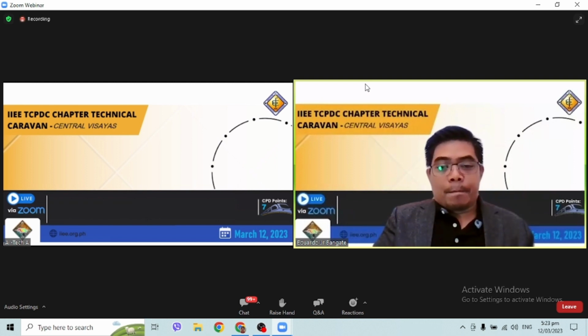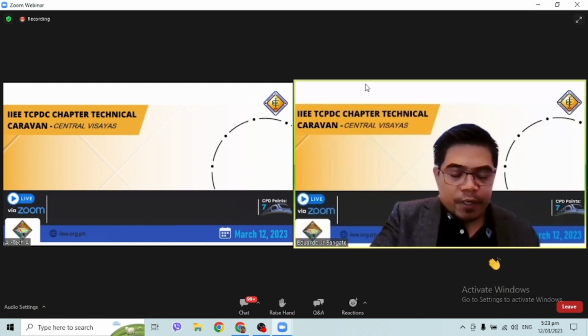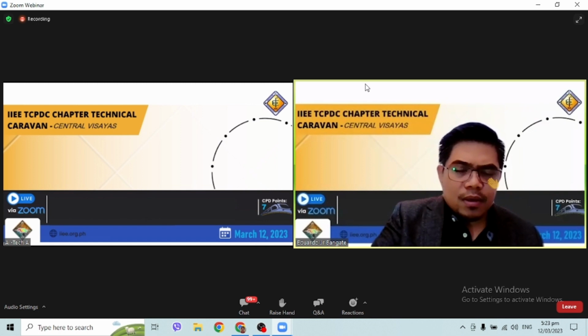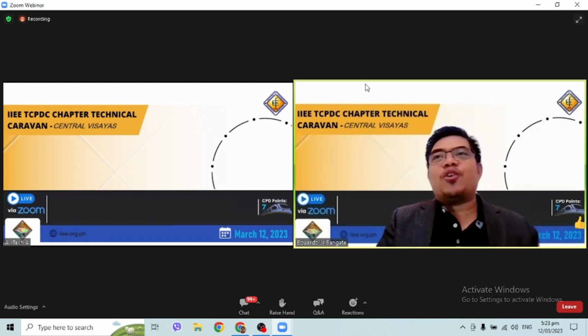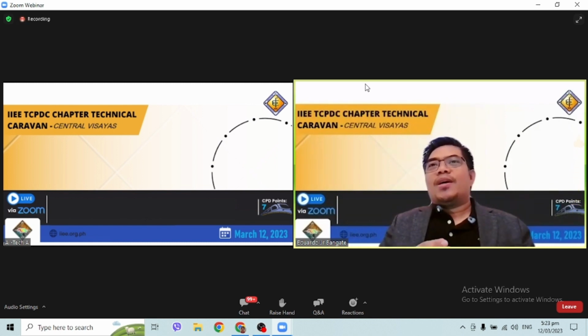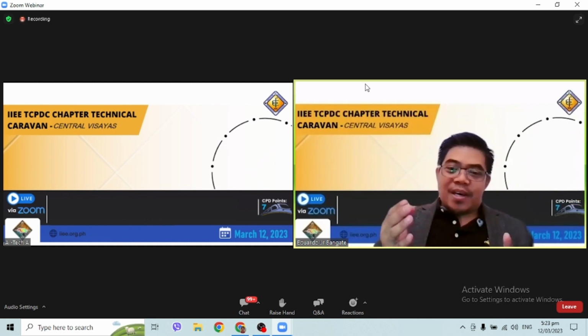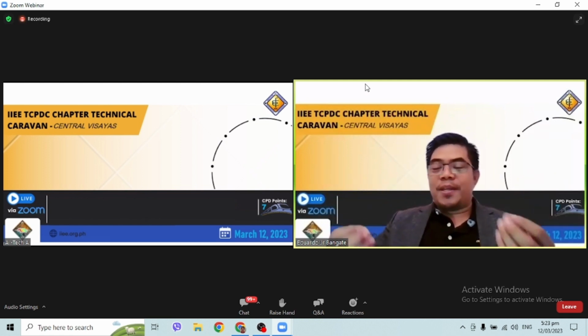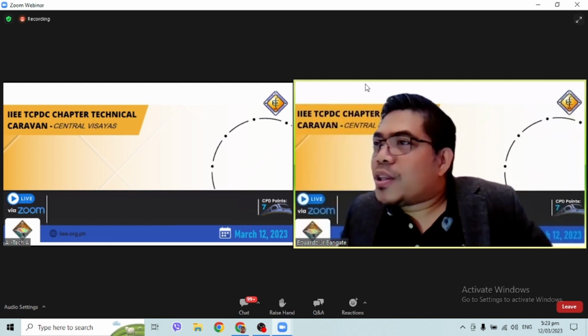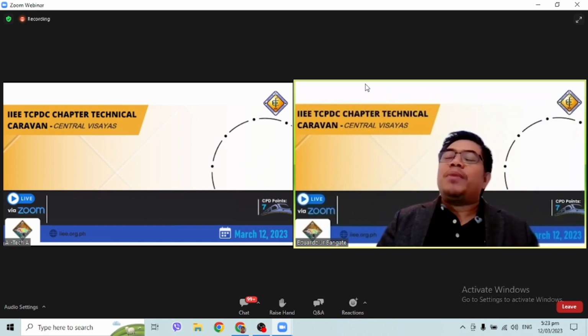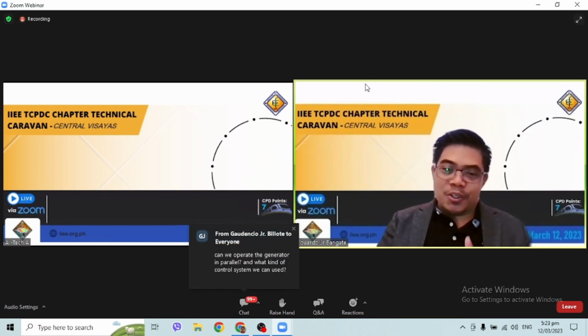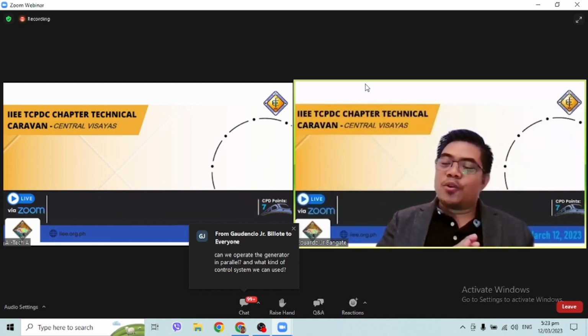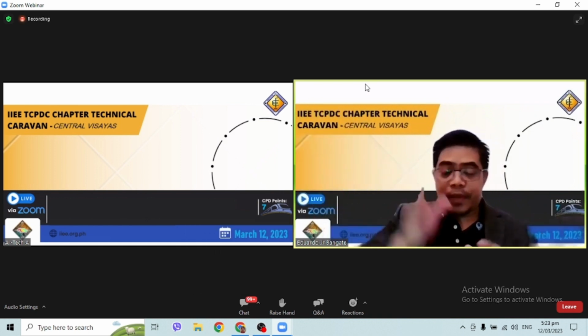Yeah. And what was the first question again, please? What is the pre-commissioning testing on generator? Okay, pre-commissioning testing. You have to run the generator while it is in the yard. We are talking about PDI, pre-delivery inspection test. Every supplier of generators does the PDI before shipping the generator to the customer site.